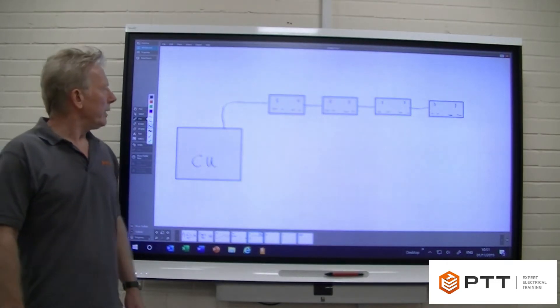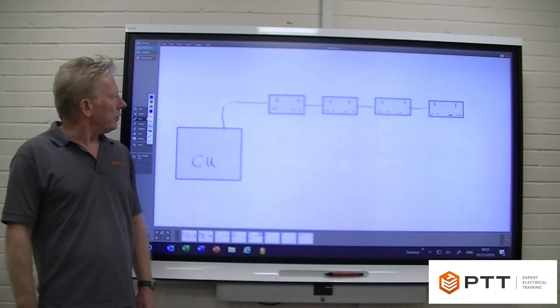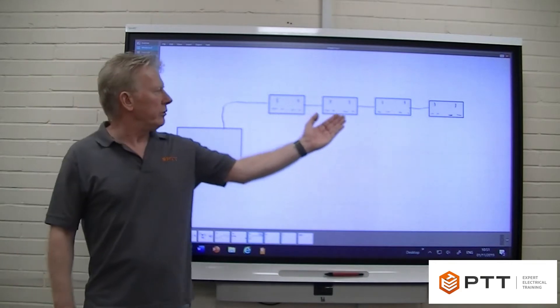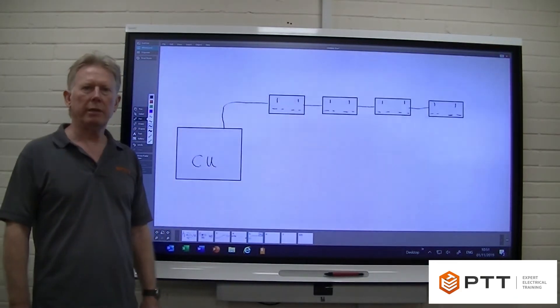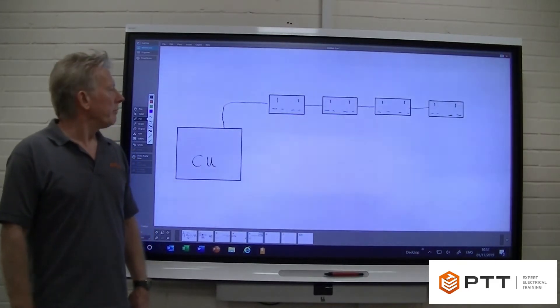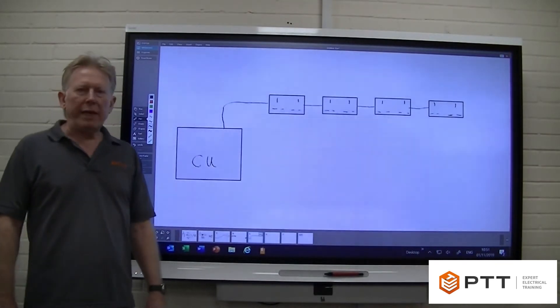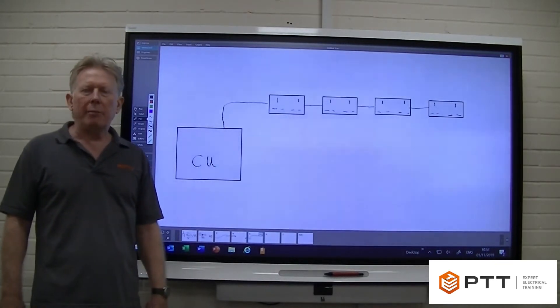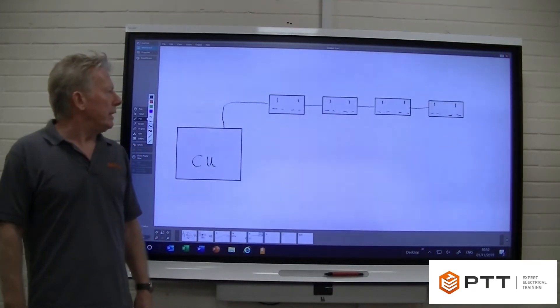I just wanted to start off by talking about a standard radial circuit. I've just drawn a simple radial circuit here which we could, if we wish, protect with a 20 amp type B circuit breaker. Now 2.5, 1.5 flat twin and earth can actually take up to 27 amps, and so obviously a B20 in this particular instance is perfectly adequate for protecting that cable.